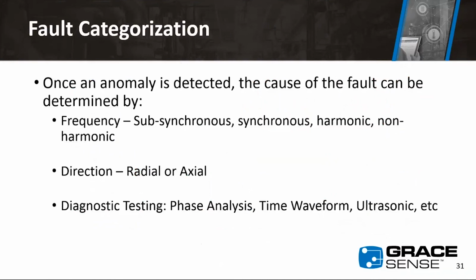The way we do that is once we detect an anomaly, we start to narrow down the potential fault. One way is by looking at frequency. Is this below the turning speed of the motor, or subsynchronous? Is it at exactly the turning speed of the motor, so it's a synchronous fault? Or is it a harmonic, which is an exact multiple, for example exactly 2 times the running speed? It is not 2.048, it is 2 times. Non-harmonic is anything that's not an exact multiple of that running speed.